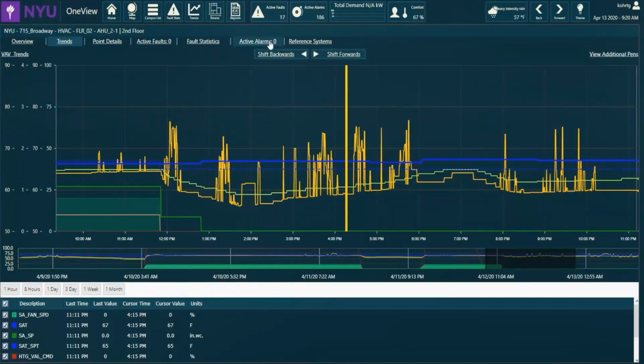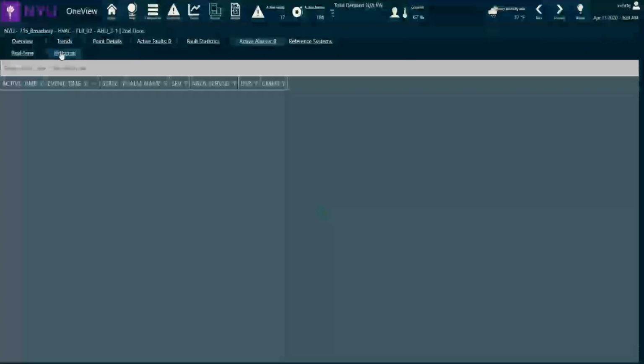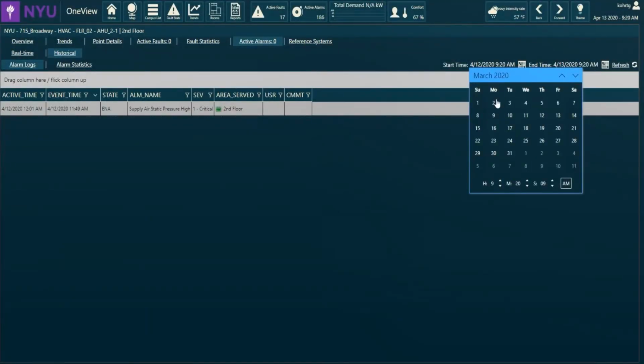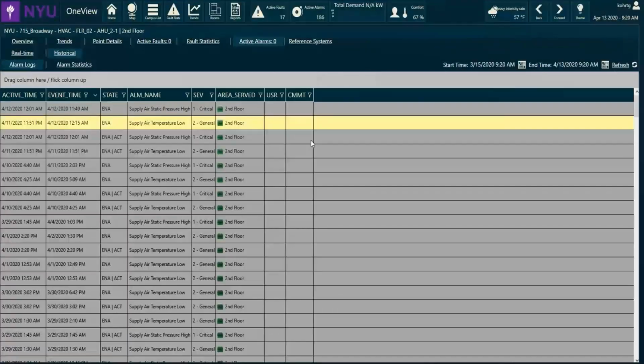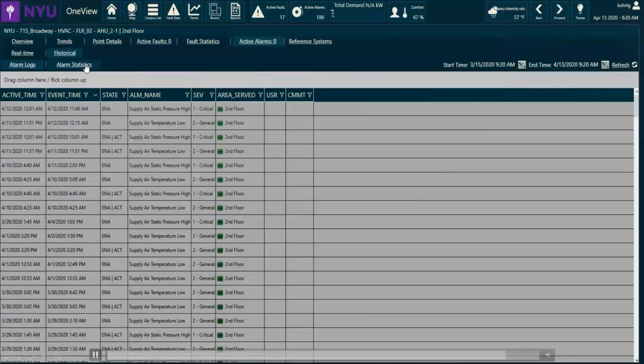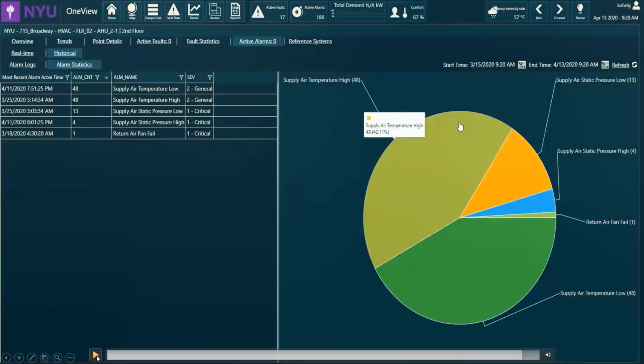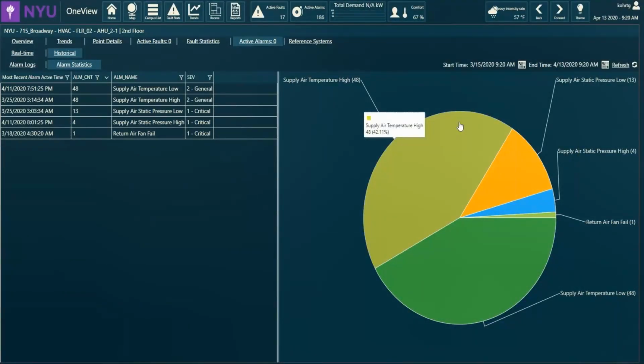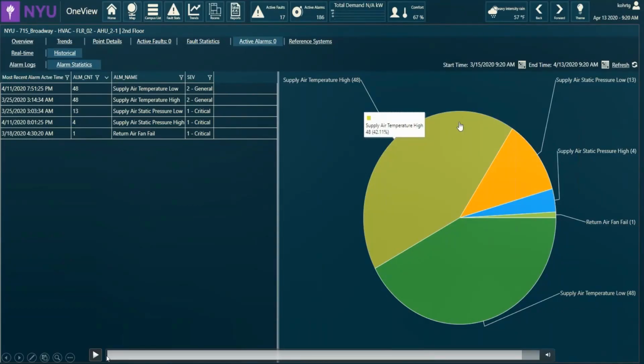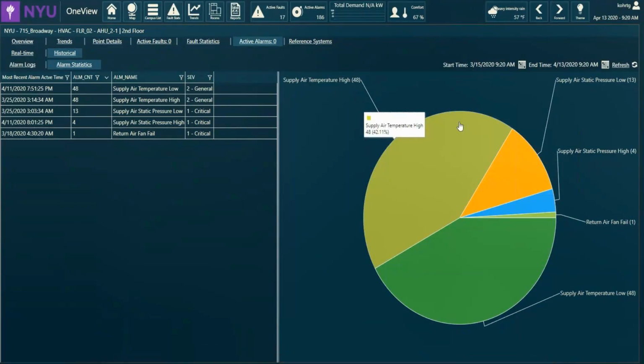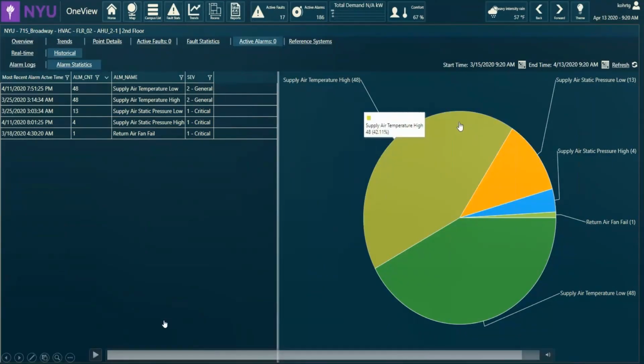Basically providing all current and historical information related to that particular asset. Here I'm jumping back and looking at a month of historical data and events, going back and looking at everything that's been a problem with that piece of equipment, then analyzing the different issues to find typical causes, like a pie chart of what types of things have been happening with that equipment. On some jobs we also have work order data coming in, so you can see all the maintenance that has occurred over the last period of time, and that's the digital twin of that piece of equipment or asset.